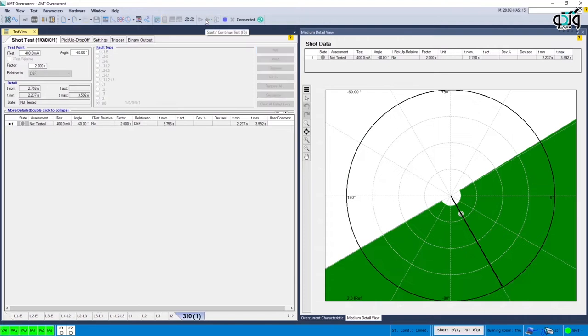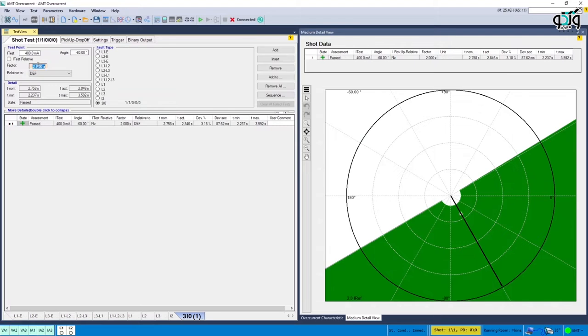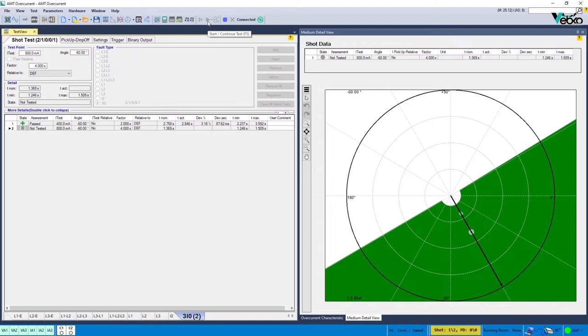This process can be continued by injecting 4 times the specified current. Also, some shots can be set to ensure inactivity of the relay in the blocking area and the test can be continued at the border of operation angles by adding new points.